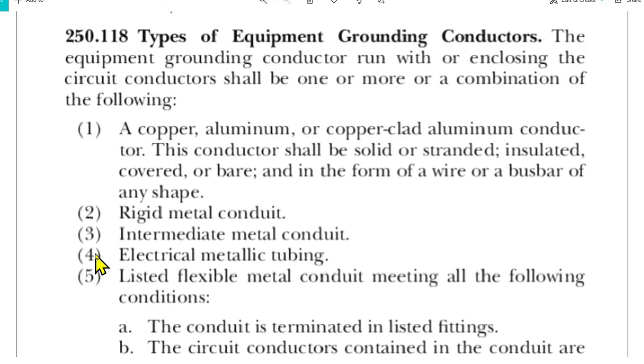This is 2020 NEC 250.118, types of EGCs. Now go down there to number four. Number four, electrical metallic tubing. So that is a type of equipment grounding conductor. This is a very important point in the contest last year. And so I just wanted to make sure I point it out.